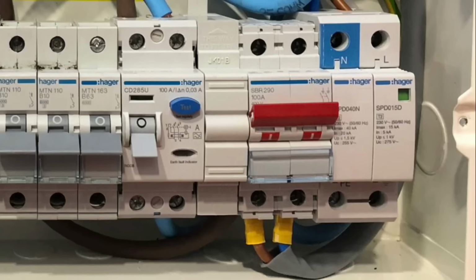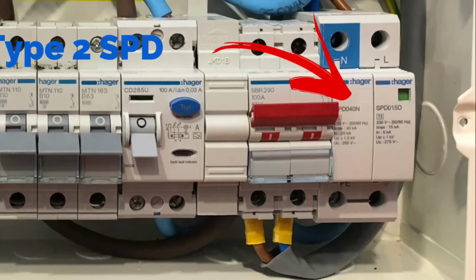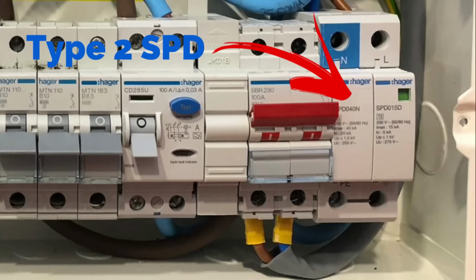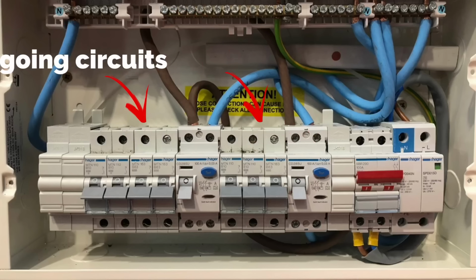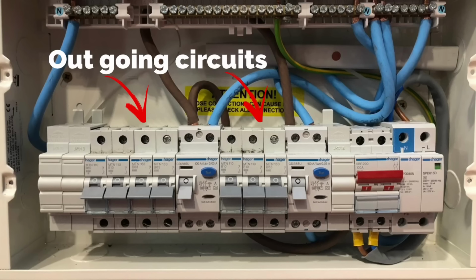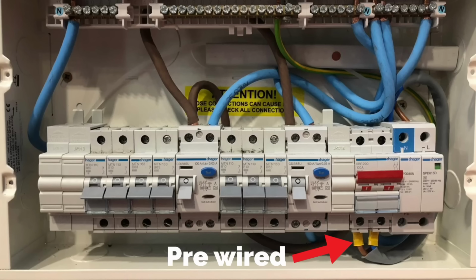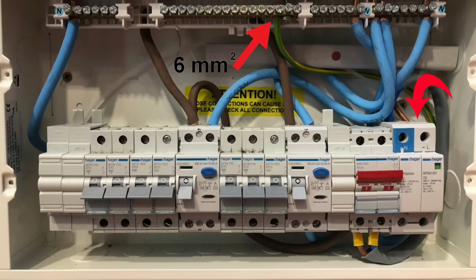So we do this consumer unit now that's pre-fitted with a Type 2 surge protection device. So as far as the installer has to concern himself with fitting this, is nothing. All he does is put his outgoing circuits like he did before. You can see the surge protection is literally wired from the bottom of the main switch, so we don't need any overcurrent protection device in here either. It's wired from there, simply line and neutral to the top of the surge protection and the earth going away to the earth bar.